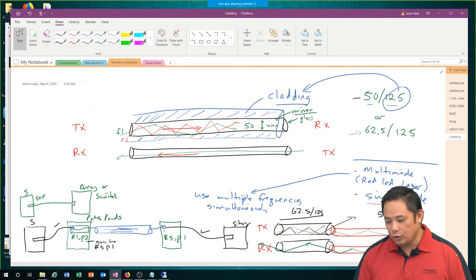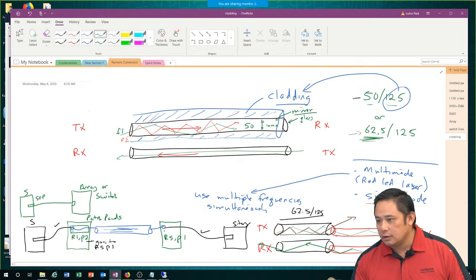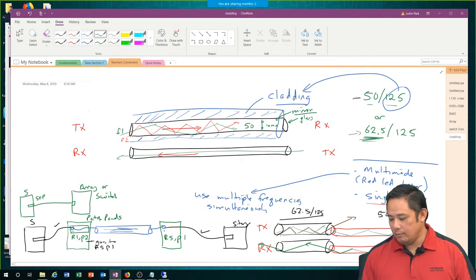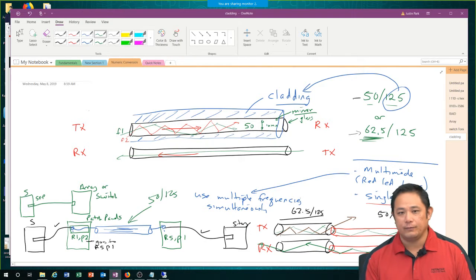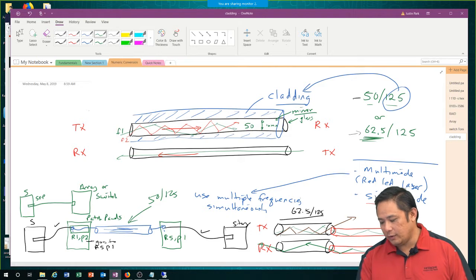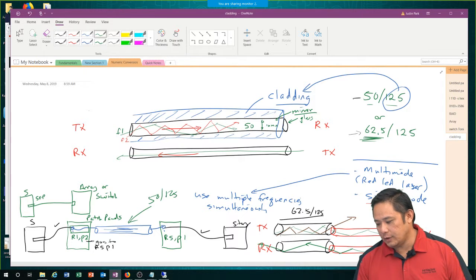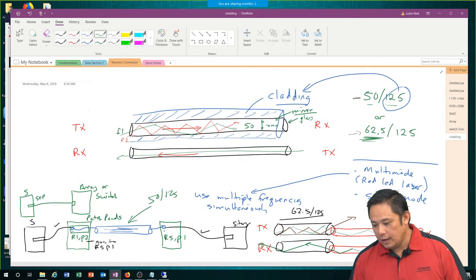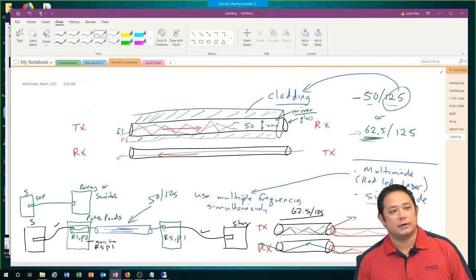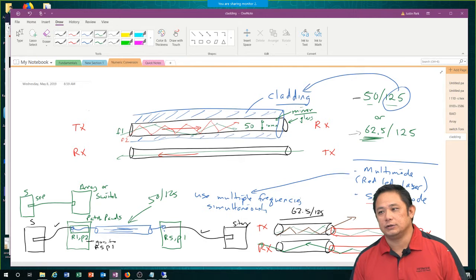And usually what happens is in older data centers, they're using the larger cable. And in the majority of newer data centers now, the trunk lines here between the panels are going to be 50/125. Okay? So just be aware of that scenario can occur. And that's really all you need to know in terms of fiber, F-I-B-E-R. Any questions? Pretty straightforward. We'll go downstairs later on, maybe this afternoon or tomorrow, and I'll show you that.